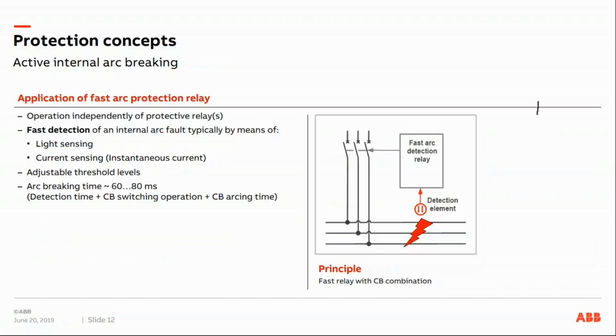Here we have a fast-acting protection relay with supplementary equipment like the Is-limiter. We have a fast detection of an internal arc fault, typically light sensing and instantaneous current sensing. And here again, the clearing of the arc fault is done by the upstream circuit breaker. So usually you have a detection time plus a circuit breaker switching operation time plus a circuit breaker arcing time, which leads to 60 to 80 milliseconds.